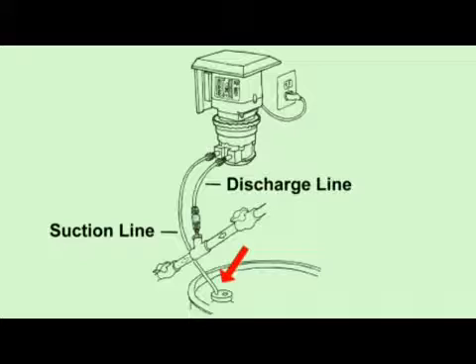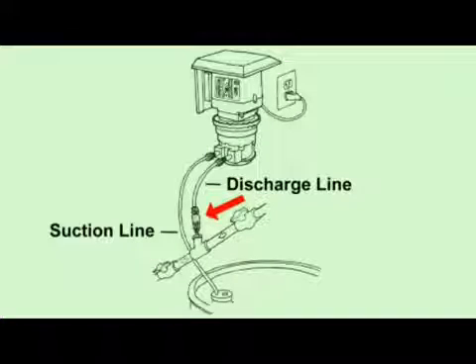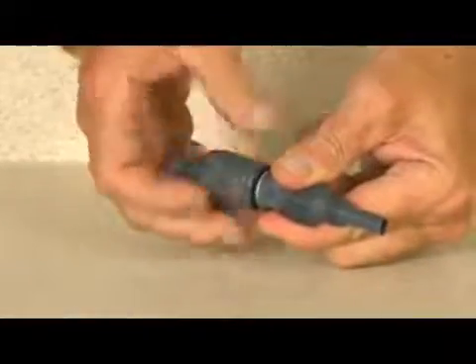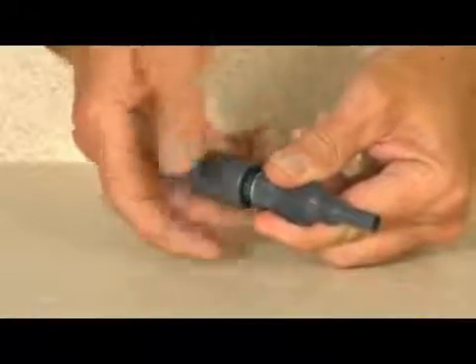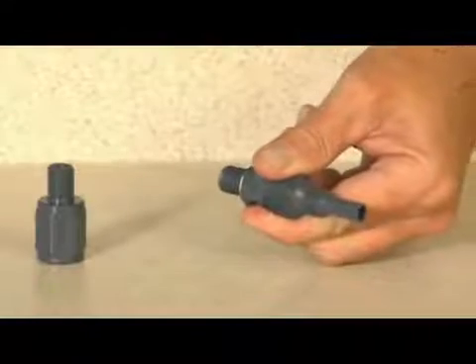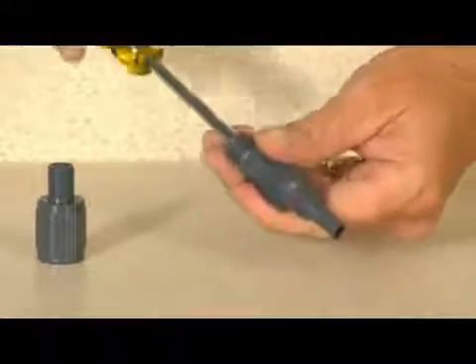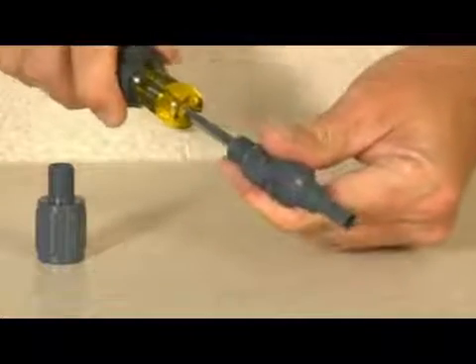Insoluble sediments or particulates drawn through the suction line from the bottom of the tank can cause blockage or restriction in the check valve duckbill, creating back pressure that exceeds the pump tube pressure rating. To address this issue, do the following as it applies. Insert a round shank screwdriver through the injection fitting into the pipe to locate or break up accumulated deposits. If a screwdriver can't be inserted, drill the deposit out of the injection fitting.